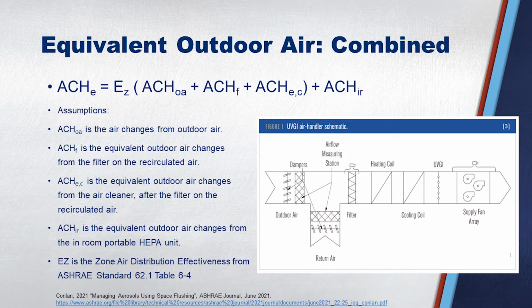I liken that to the time frame we're talking about, between movie times, right? You walk into a movie theater and the last movie just left and it's stale. That's the time frame where you want to try and hit this to really remove virus. So the equation is actually pretty simple. We're just looking at effective air changes of equivalent outdoor air. You have straight outside air, from my filter, from my air cleaner, and from anything in the room. You look at the air handling unit diagram, I have filter first, and then I've got UV second, and that's important, and you'll see it later.